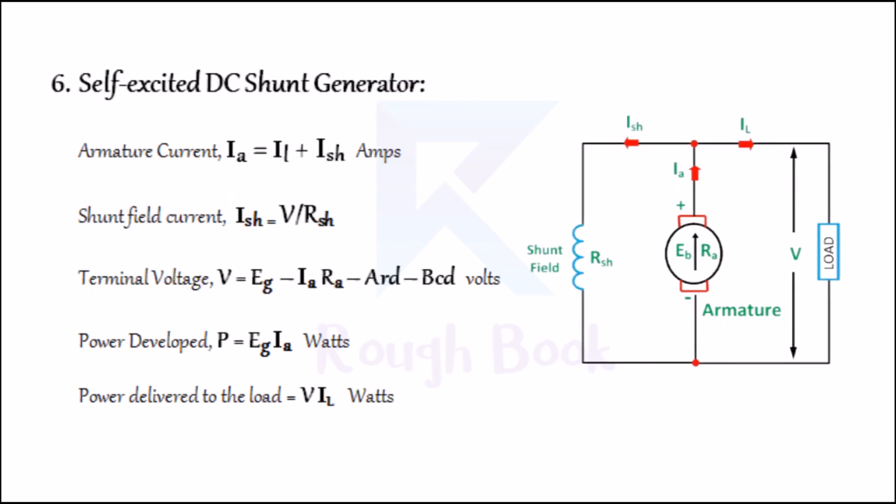Number six: Self-excited DC shunt generator. In this type of generator, the field windings are connected across or in parallel with the armature winding so that the full voltage of the generator is applied across them. Armature current IA = IL + ISH, where ISH is the shunt field current given by V / RSH, and RSH is the resistance of the field winding. Terminal voltage V = EG − armature resistance drop − armature reaction drop − brush contact resistance drop in volts. Power developed P = EG × IA in watts. Power given to the load = V × IL in watts.